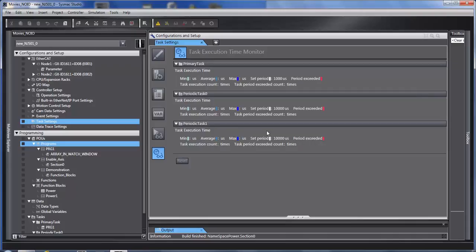This allows the motion code and all the code that has to execute quickly to execute in the time that we specified, be it half a millisecond, one millisecond, two milliseconds, or four milliseconds. It is important that the primary task executes on time, and this is how we balance the workload.